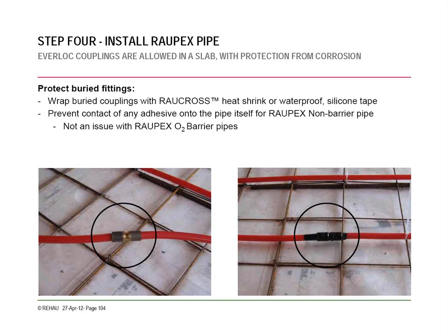And if you accidentally ding the pipe or make a cut in it, you'll have to replace it with a fitting. REHAU has the Everlock system, which is approved to be buried in a slab. You just have to wrap it with silicone tape, basically electric tape, to keep it from corroding the brass. But otherwise, the fitting's approved for being mounted in the concrete.